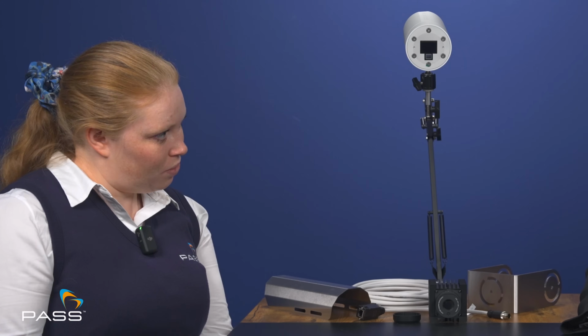Correct. Yeah. So we've had something called the FLIR AX8, which is a really small product. It's still available in the market, but it is an 80 by 60 resolution camera with one field of view. This gives you a little bit more versatility in terms of your field of view options and also your mounting options, allowing it to integrate into a housing that is going to further extend operational temperature and give you that flexibility in spaces where a standard automation camera without a housing cannot perform very well. And it also gives you the configuration options so that the customer is still, at the end of the day, making the decision that's best for them and for their need in early fire detection.